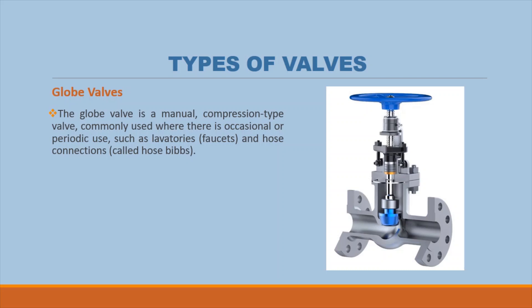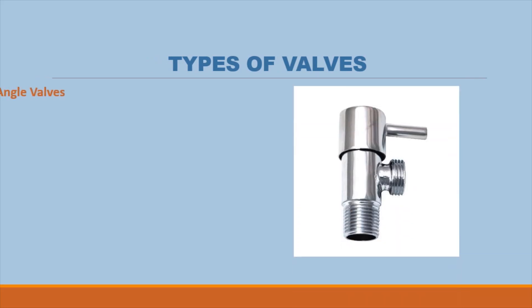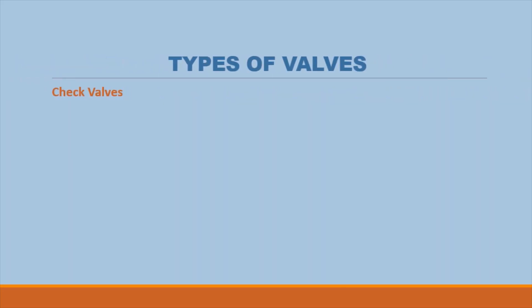Globe valves: the globe valve is a manual compression-type valve commonly used where there is occasional or periodic use, such as lavatories and hose connections. This type of valve regulates the flow of water. Angle valves: the angle valve is a manual valve similar in operation to the globe valve, utilizing the same principle of compressing a washer against a metal seat to cut the flow of water. It is commonly used for outside hose bibs.